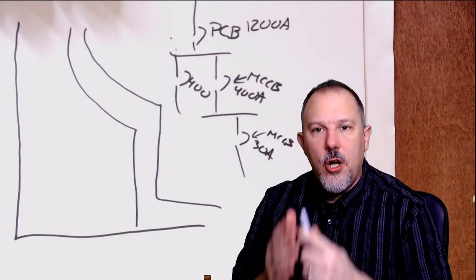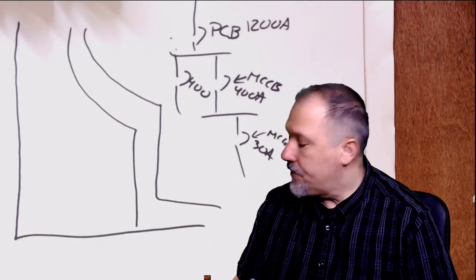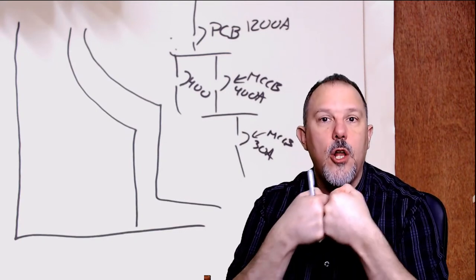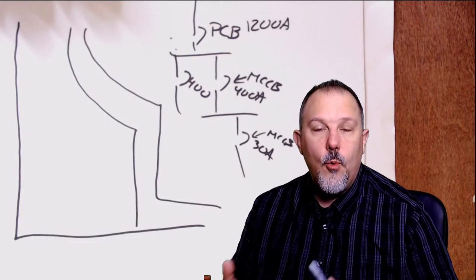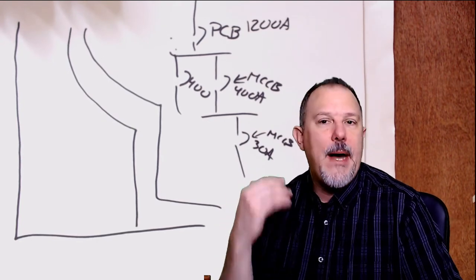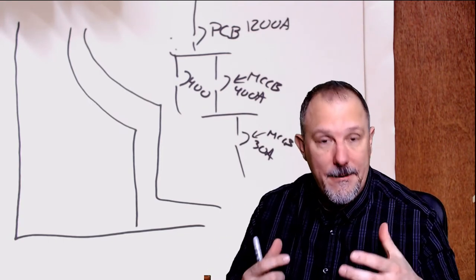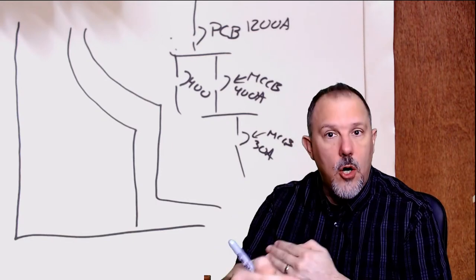Now, as you move up closer to the main, I need a larger breaker, but also one that rides through during fault conditions so that I don't trip the main. I need a breaker that'll hold its contacts closed longer, and I'm into a power circuit breaker. Well, power circuit breakers are expensive. I need a low voltage assembly, a big gray box, and I need a room to handle that big gray box. I call the power circuit breaker the Swiss watch of circuit breakers, because it's a very complicated device. But I need that big device to hold those contacts closed under higher fault current conditions for a longer period of time. What I needed was a trip curve that looked...